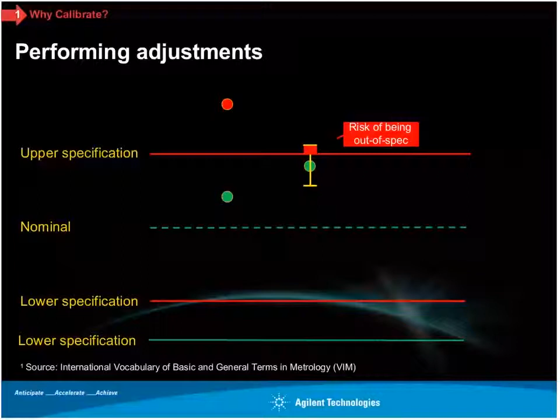Now, when I talk about traceability today, I'm going to give you some tips and tricks in about 25 minutes on how to read a traceability report. But I want to remind you, suppose you had 2 different labs, Laboratory A and Laboratory B, and they both came up with the same result and said this instrument for this particular measurement is just inside the specification. You could say, okay, great, we're good to go for another calibration period, whatever you use, 1 year, a year and a half, whatever it might be. But really, unless you know the measurement uncertainty, you don't know how good the measurement was.